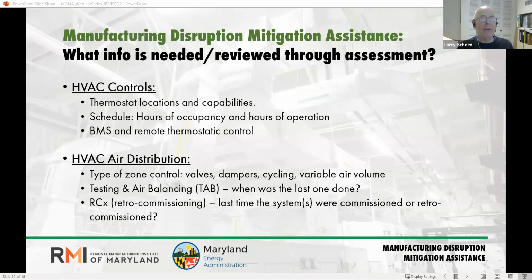And so the details of the controls are those thermostat locations and capabilities. I was working with one facility where everything was localized. And so whether it's outdoor air or temperature set points, everything had to be a person walking up to a control. Of course, more modern systems and more capable systems have a building management system, BMS or EMS, energy management, and ability to control that remotely. So we have a vast difference of how those controls are set up and the level of automated scheduling that they have. And then on the distribution side, as I said, different ways to get air to different spaces.